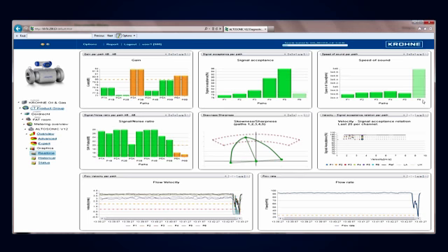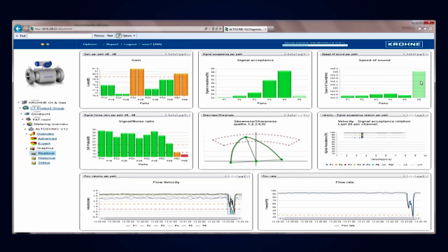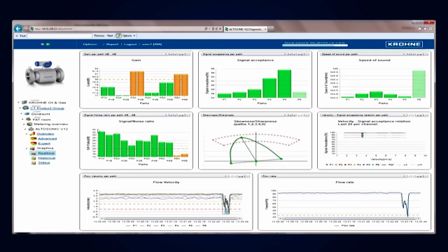One thing you see is that the speed of sound of path 6 has gone up. The reason, of course, is that the sound signal of path 6 no longer bounces on a clean metal surface. It now bounces on the contamination, on the pollution, the piece of tape that we put inside the meter.